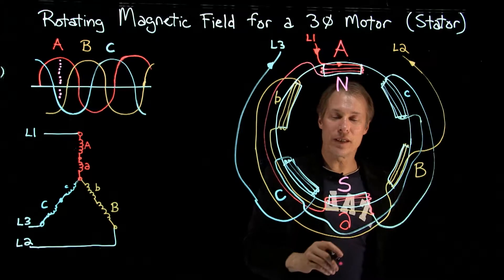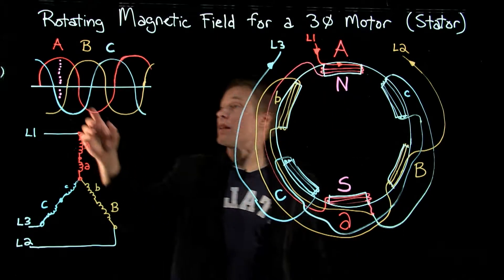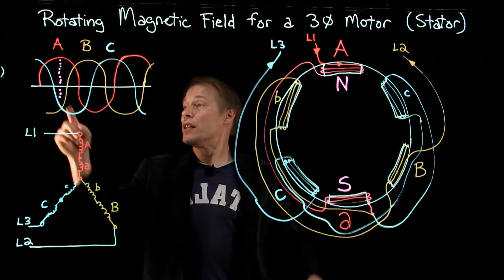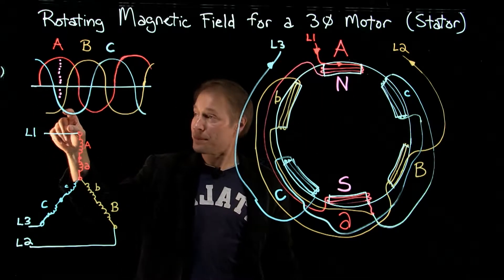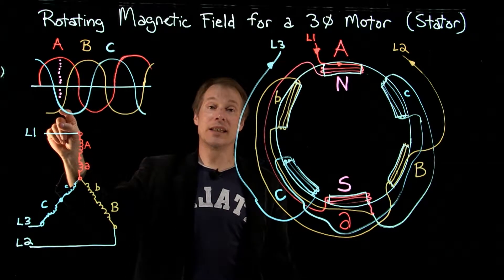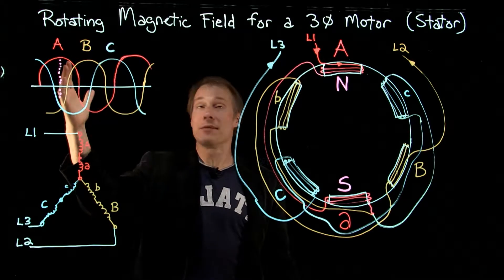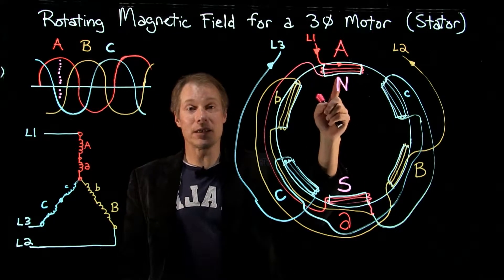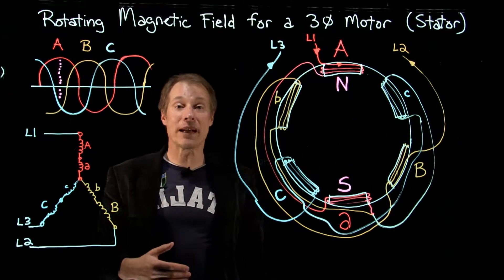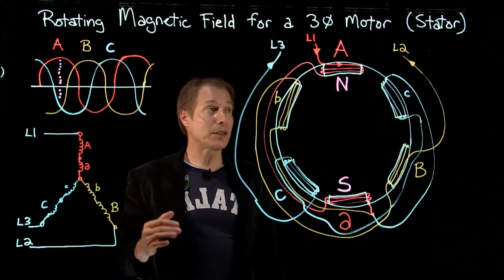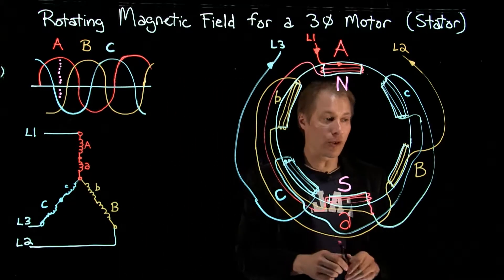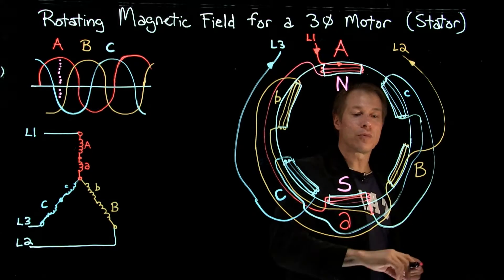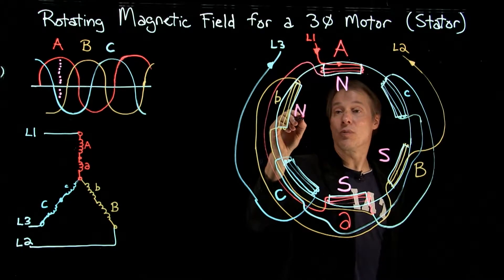This coil is wrapped the same, giving us the south pole here. One thing to note: the sine wave is above the line for L1, meaning the current is going one direction for L1. For L2 and L3, they're below this line, so those currents are going in the opposite direction at that same time. If this is the source, the current is coming from the source for the A phase, which means for L2 and L3 the current is going back to the source. Following the left-hand rule, with current going back to the source in that direction, my fingers go this way — that's the north pole, giving this a south pole.